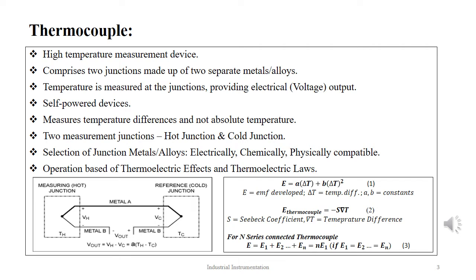The thermocouple device comprises two junctions made up of dissimilar metals or alloys which are welded or riveted together and encased in a metal sheath, and it is the junction where the temperature is measured. When the measuring junctions are heated, a voltage is produced that is greater than the reference junction, which is also called the cold junction. The changes in the junction temperature give rise to junction potential difference in terms of voltage, which is measured and the temperature is determined.